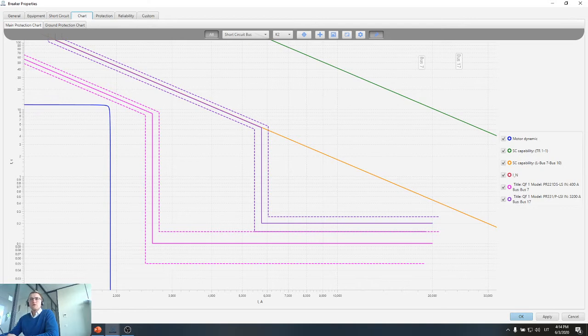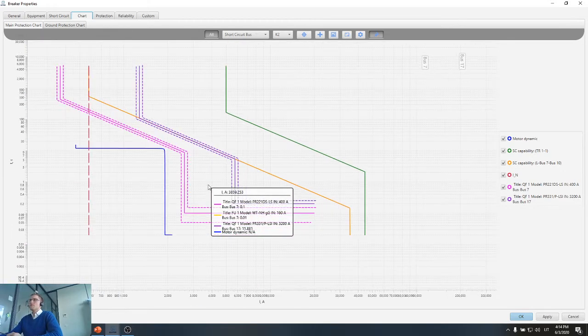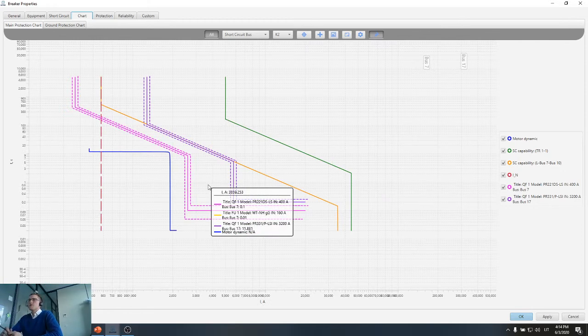The question now: for setting short circuit protection for transformer inrush current, or short circuit current, consider which is a good safeguard for the transformer. So transformer protection is a little bit more advanced topic. Usually in order to set transformer protection, we use numerical relays, which are capable of measuring the second harmonic, because during transformer energizing, the inrush current is very rich in second harmonics. So if you are capable of blocking the operation of the numerical relay during transformer energizing, and you can understand that the transformer is energizing because of the second harmonic flow, then the operation of the numerical relay for the transformer is just set in a normal way.